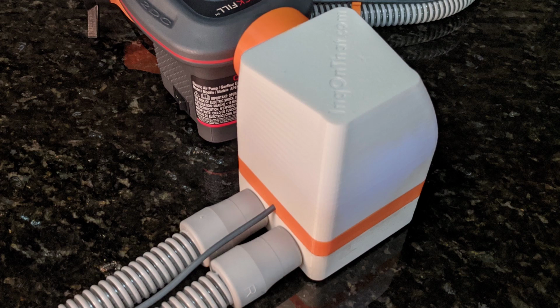Next, we have the main InqVent unit. The housing is 3D printed using ABS plastic. This unit houses 2 air valves, CPU, and supporting Wi-Fi and electronic circuitry. This unit connects directly to and controls the air pump. The housing has connections for standard airway hosing. On this visible side, we have hoses to and from the patient, and on the other side, we have an exhaust that can be routed via another hose to an external filter, again to protect our medical professionals.